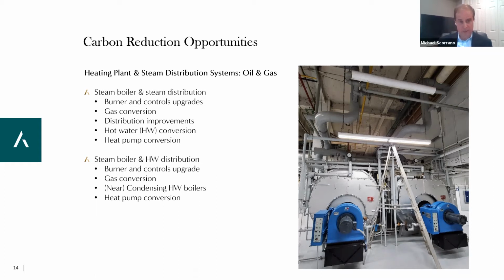Some more expensive measures include hot water conversion, taking the steam system and converting it to a hydronic type building for better efficiency, or heat pump conversion, getting rid of the steam boilers or steam system where there could be losses, and putting in something more electrically efficient that helps drive down the carbon component.